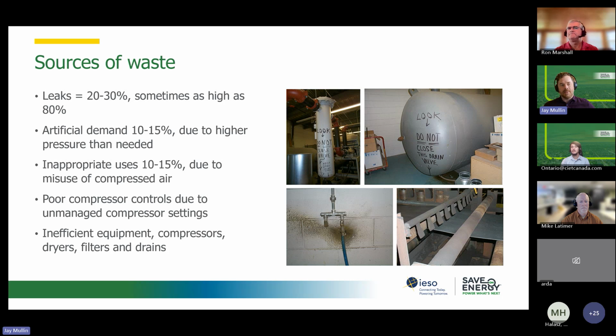We have a question about whether the specific power of compressors, the kilowatt per 100 CFM, changes depending on the manufacturer, type of machine, or what influences that? Yeah, it changes. Now there's an organization called the Compressed Air and Gas Institute, CAGI. They have ratings, data sheets that manufacturers use. They're required, if they're part of CAGI, to publish these sheets for their compressors. Every manufacturer is required to have a library of these sheets, and you can browse through them and see that some of the older design compressors are not as efficient as the newer design. That can point you, when you're buying compressors, to which ones you should be going with, to make your system as efficient as possible.